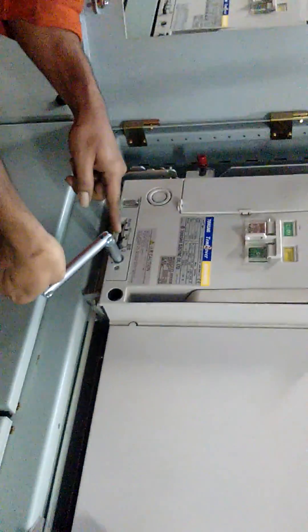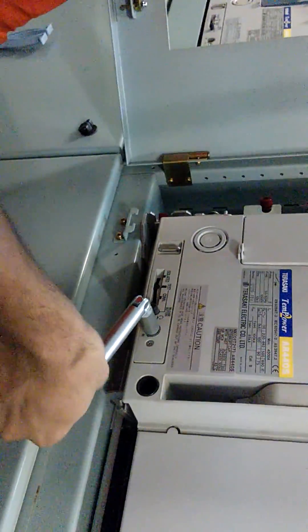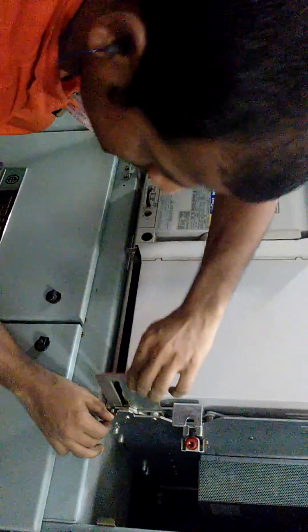The indication should come down to test. Now we will isolate. There is a sliding rack for the ACB holder — just a little bit, same way on both sides. Now we will draw out the ACB.